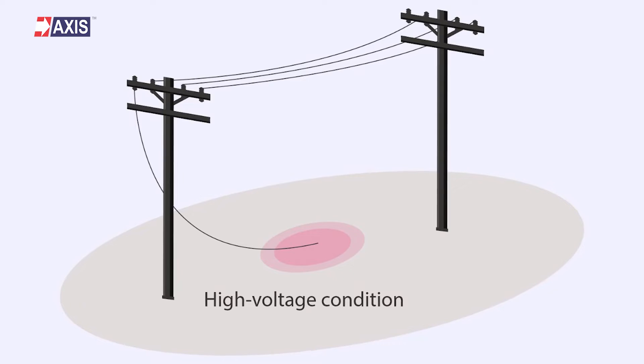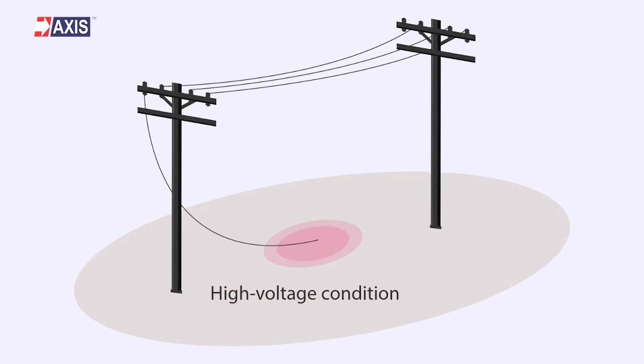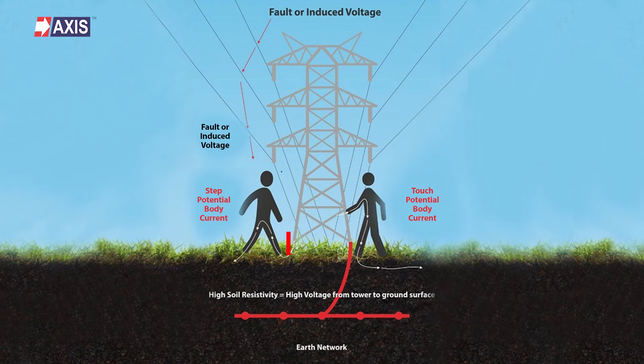Now let's understand step potential more deeply. Imagine a scenario where current flows from an overhead conductor through a chain-link fence, or when an overhead conductor touches the ground. This creates a high voltage condition. The soil's resistivity then causes a voltage gradient, leading to a voltage difference between two points at the ground. This is what we refer to as step potential. It's called step because this voltage difference can occur between your feet as you walk near the energized area, and this difference can cause electrical current to enter and surge through your body, which can be fatal or cause serious injuries.